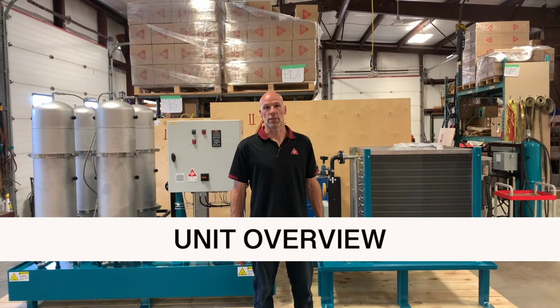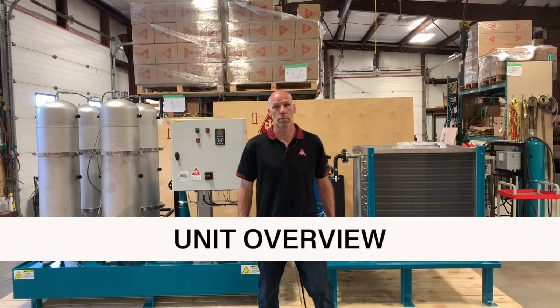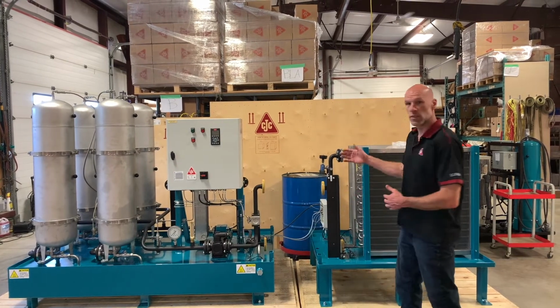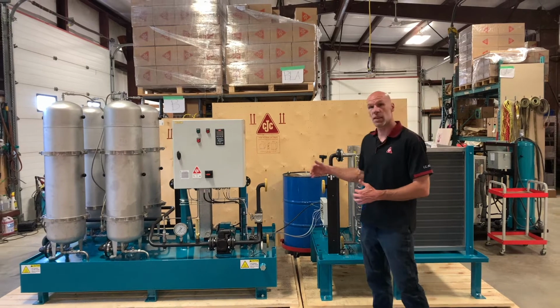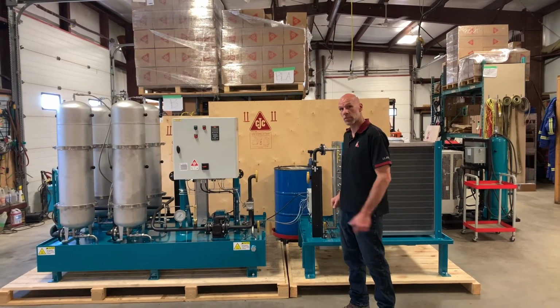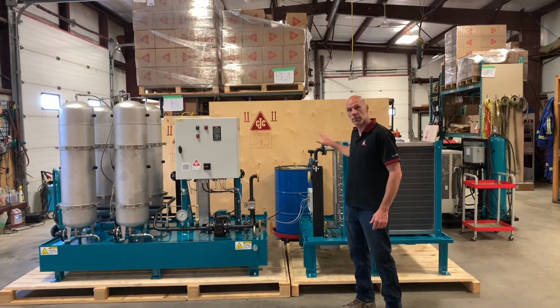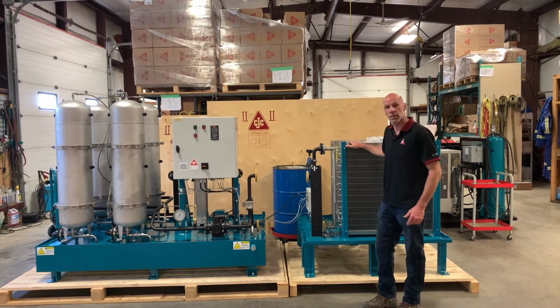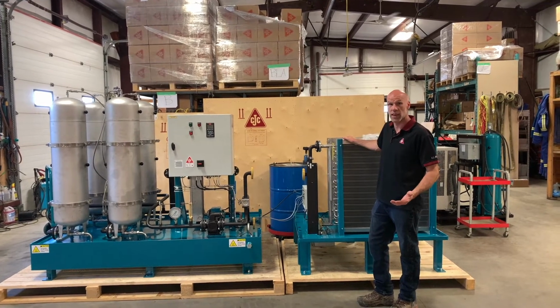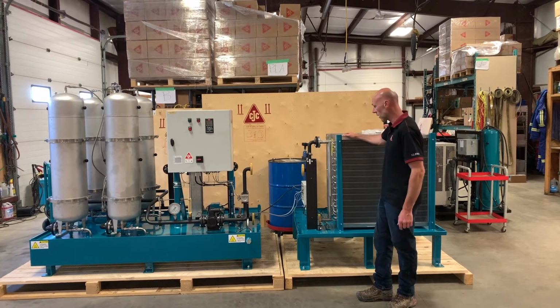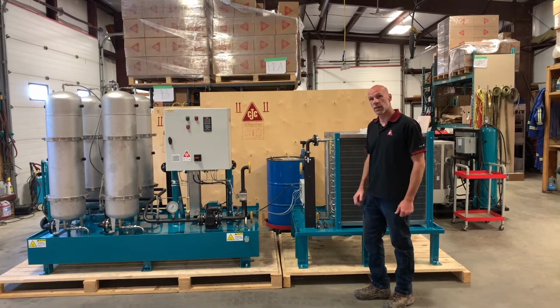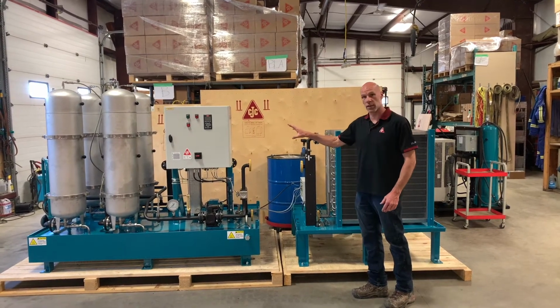This is the C.C.Jensen thermal oil filtration system. The first thing you're going to notice is it's in two separate skids. We've done this to make it easier to transport and to put in position, and also in some cases where the cooling unit can be placed in an area that might be colder than the ambient temperature, such as outside. Now it can be easily located in a different area and just piped to the main skid.